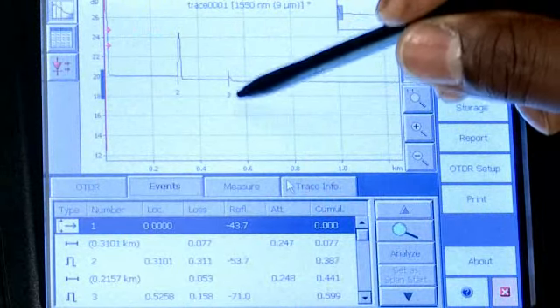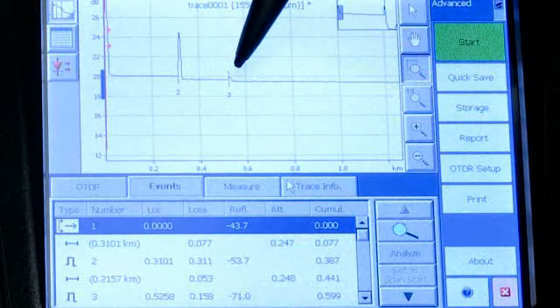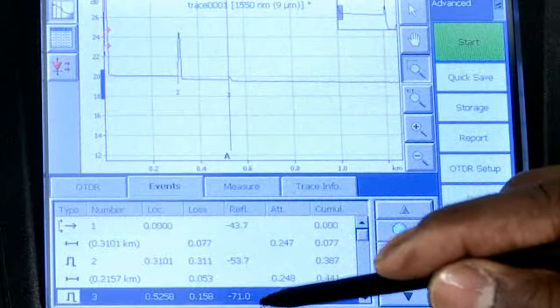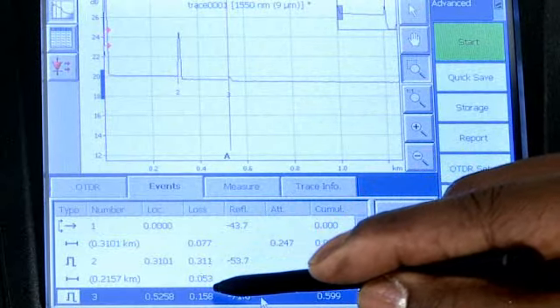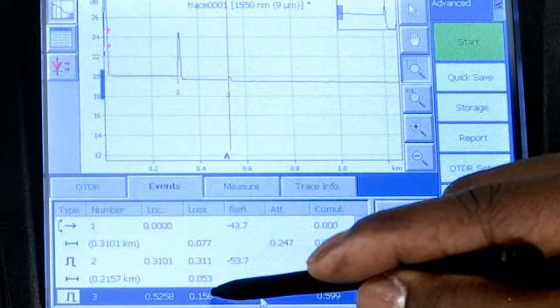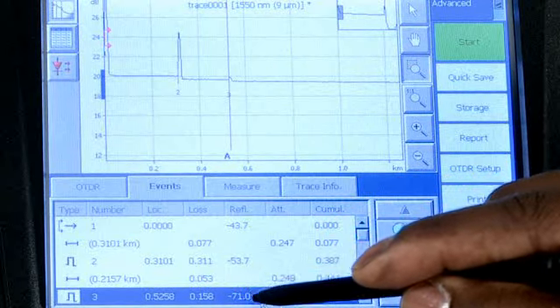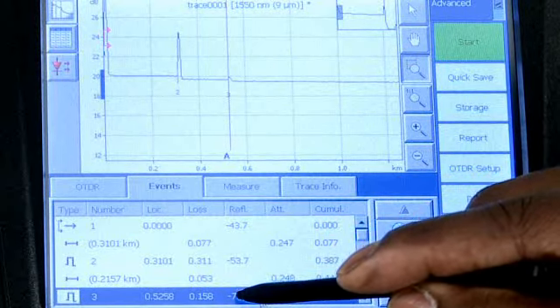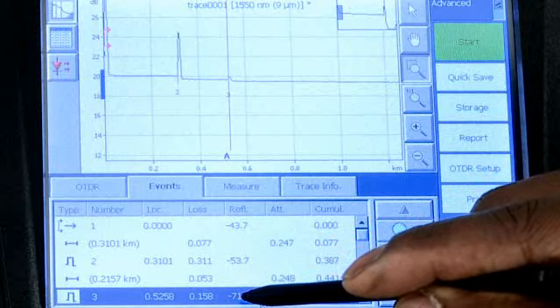The event number three where the splice was is now slightly reflective. If we look at the event table, there is a loss or attenuation associated with it of 0.158 and a reflective value of minus 71 dB.